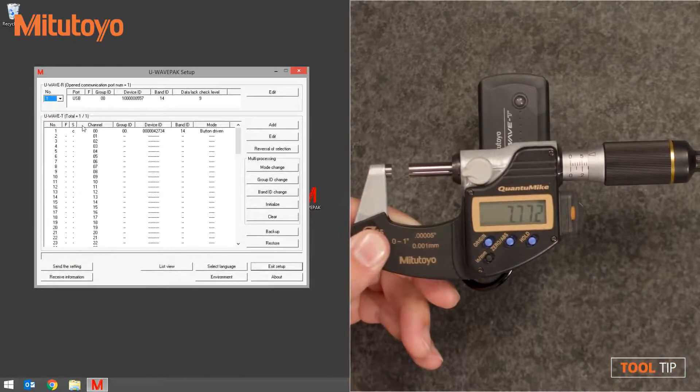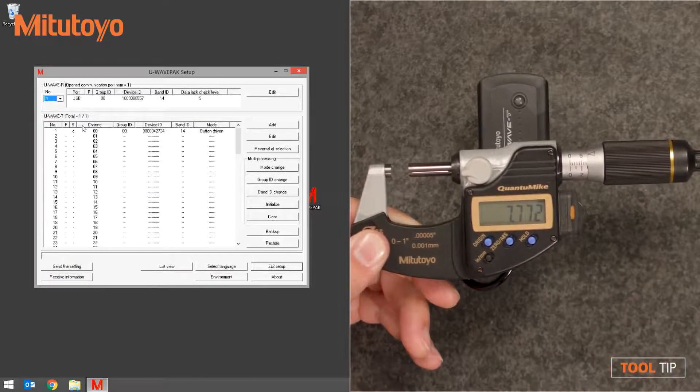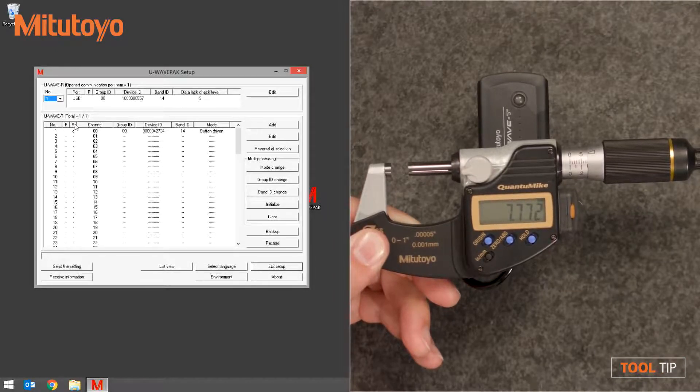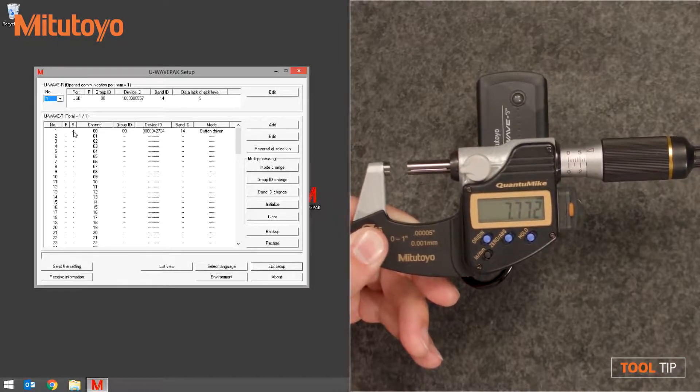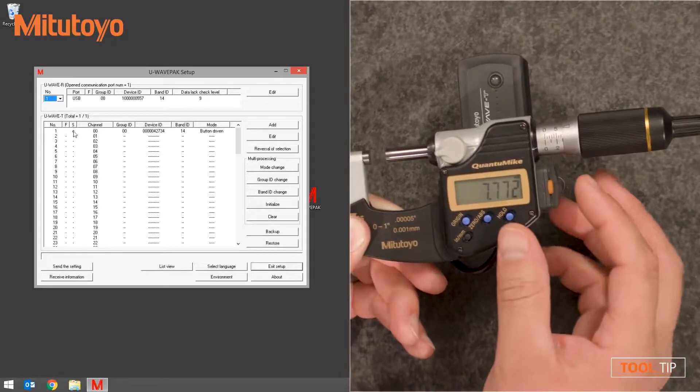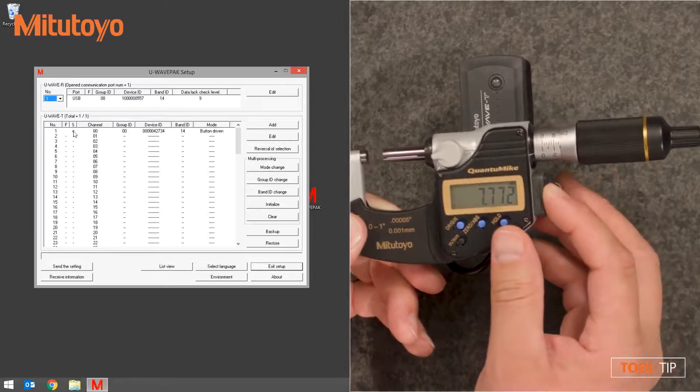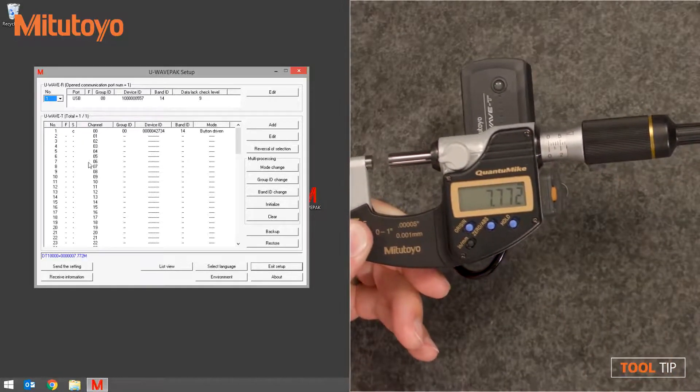In the U-Wave PAC software, notice that the R that was originally next to the transmitter in the status column is now a C, meaning the gauge is connected. If I press the Data Send button on the tool, I can actually see at the bottom of the U-Wave PAC software that the data has been transferred. The transmitter is now connected and we can exit the U-Wave PAC setup.